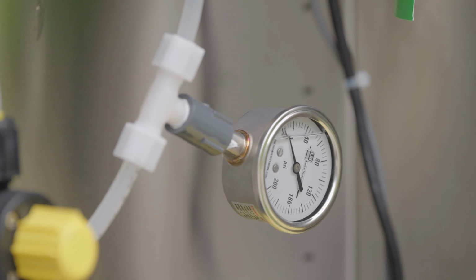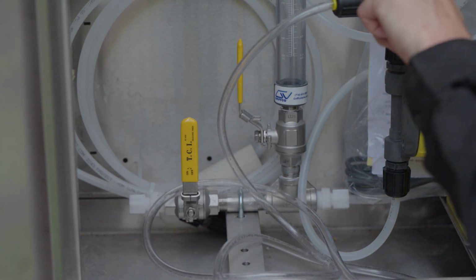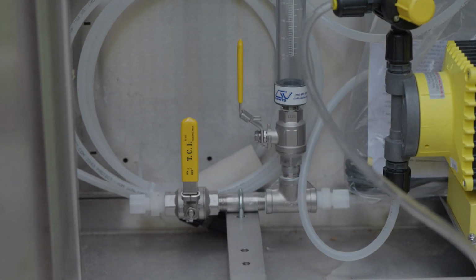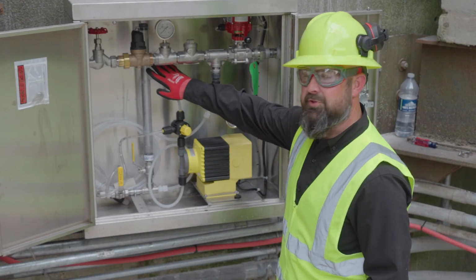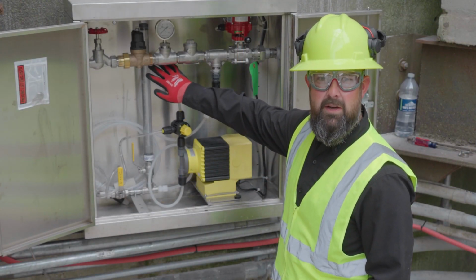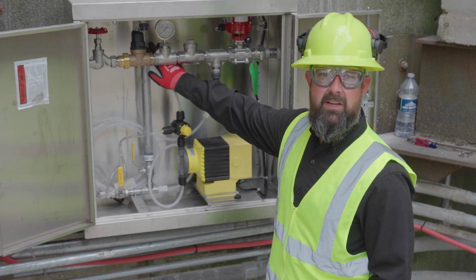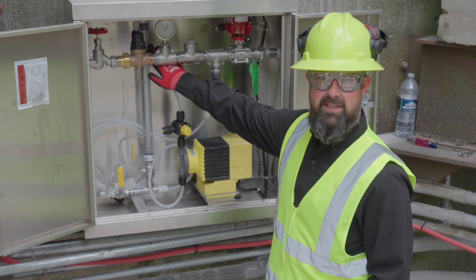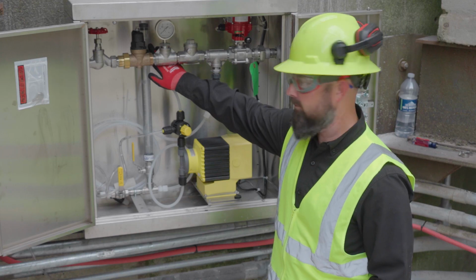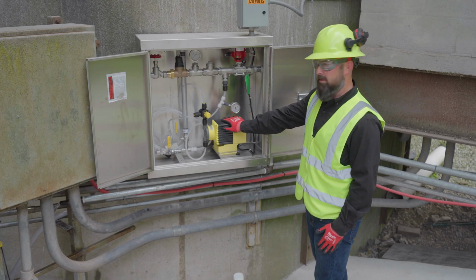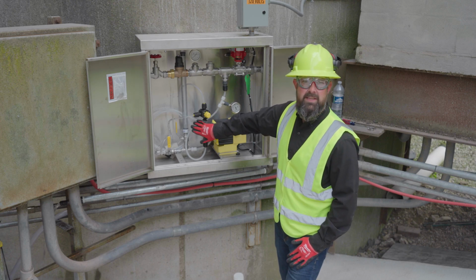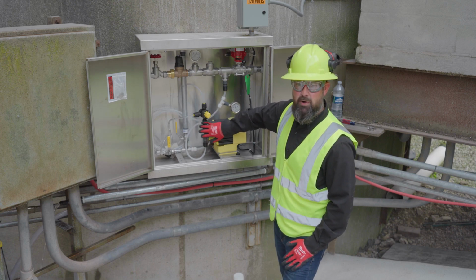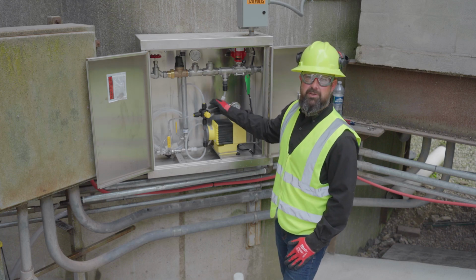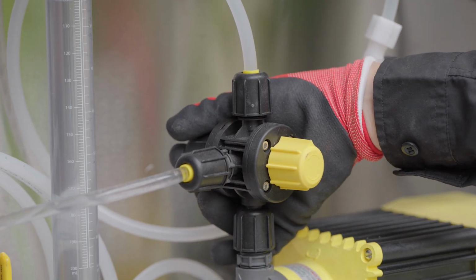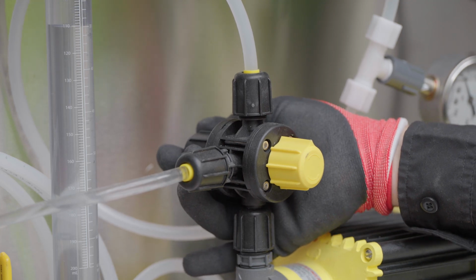It will begin dosing. We have it in calibration mode. The valve beneath the calibration column is open. The valve on the product side is closed. It is drawing product through the calibration column. For our specific scenario, we need to be moving 5.2 milliliters in 30 seconds for an accurate product dosing. As you set up your metering pump, take care to ensure that the product supply line is primed and ready. This can be accomplished by manipulating the pressure relief valve and burping the product line as needed to remove all of the air from the line.